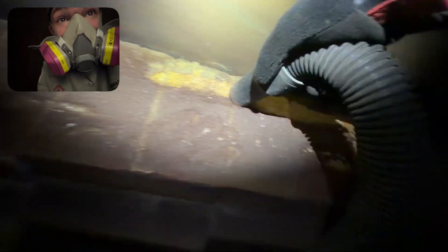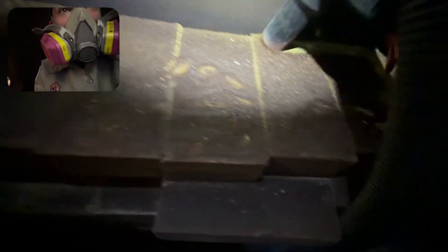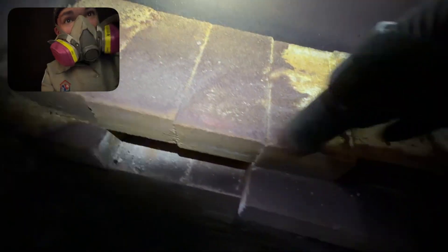That's how much more debris there was inside the burners that wasn't initially picked up. I was surprised — I didn't think there was that much left after we had scrubbed and vacuumed them for a significant amount of time. We were here almost three hours at this point, so this was definitely a good amount of work. Inside the boiler was super, super hot — way worse than any attic I've ever been in. I had to get out a few times to take a break and just stick my head out to breathe.